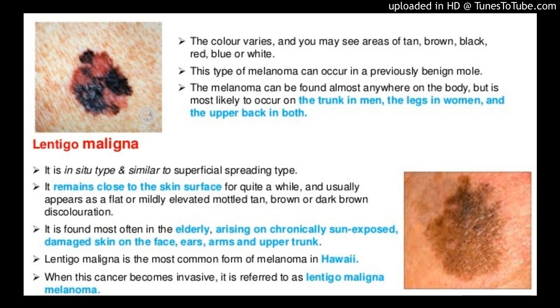RCM has a sensitivity of 85% and specificity of 76% to diagnose LM-LMM, and has also been used to delineate its margins. Most of this work is based on traditional wide-field probe RCM which requires attaching a metal ring onto the skin and allows imaging areas up to 8x8 mm. However, LM-LMM can be larger than 8 mm and can occur at uneven surfaces where the metal ring may detach. Thus, mapping the LM-LMM margins with wide-field probe RCM can be a labor-intensive and time-consuming process, approximately one hour per lesion. Conversely, handheld RCM (HRCM) can acquire images and videos along ad hoc arbitrarily free-form non-rastered paths and over large areas which the user determines in real time, allowing a live approach to mapping margins over large areas.